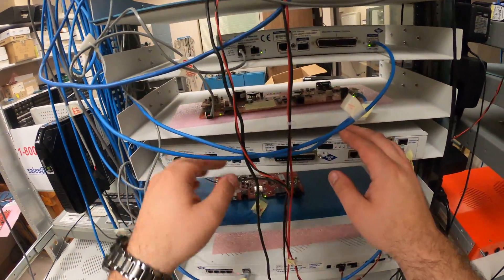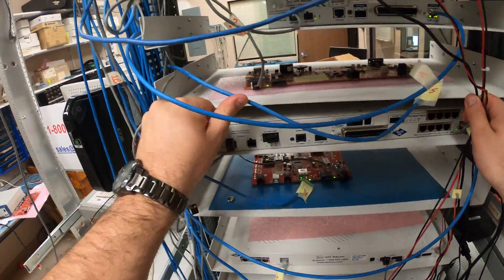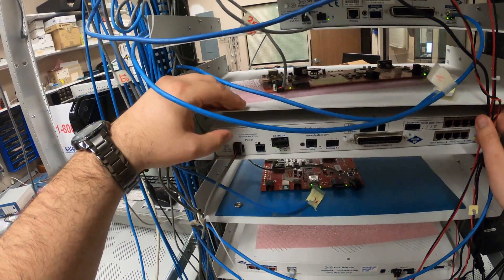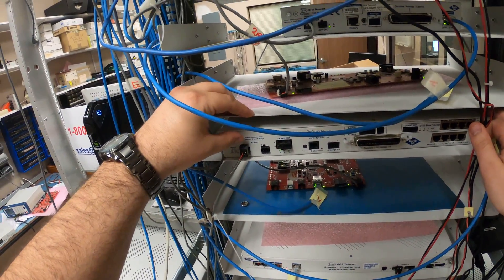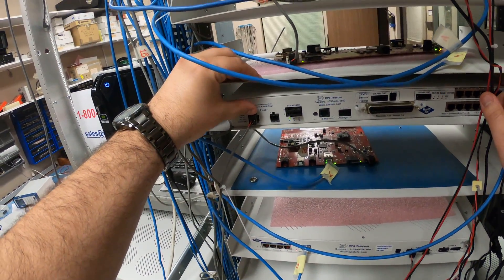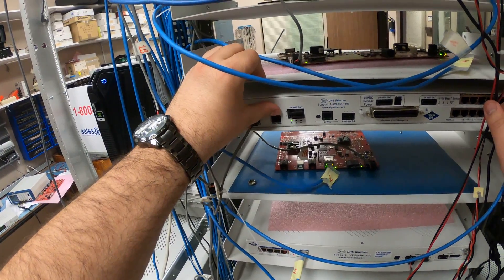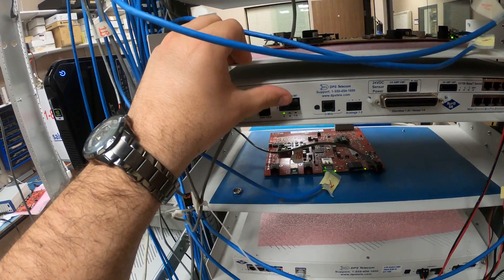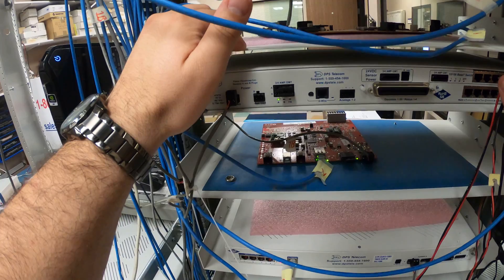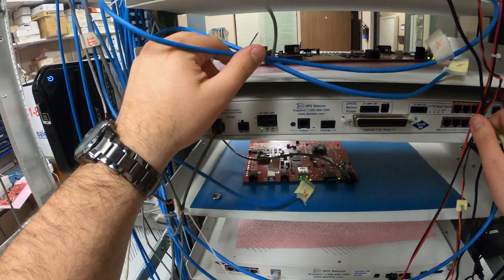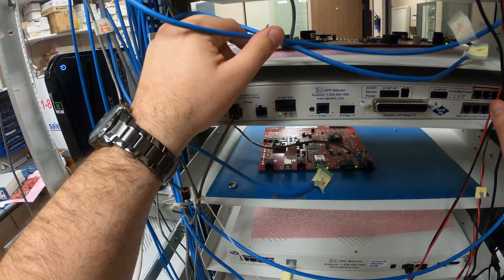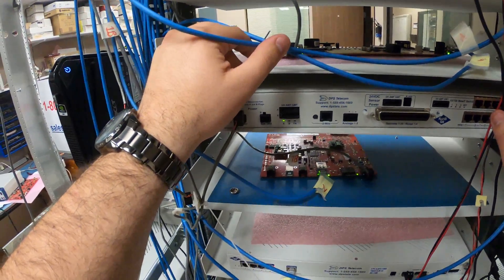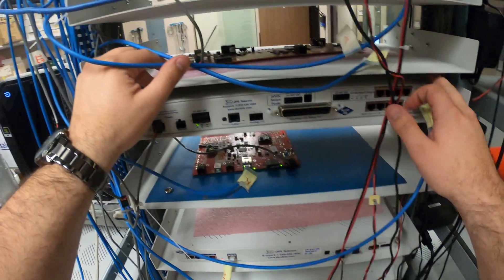We have a NetGuardian 420, and this might be a good place to start. So you can see the power connectors. These are usually on the left of every RTU that we make, and it's usually two. So we have an A and a B feed here, and there's two fuses, because it wouldn't make much sense to have one fuse, even though you have two inputs. That doesn't really help the single point of failure, so we try to have dual everything on the power side.